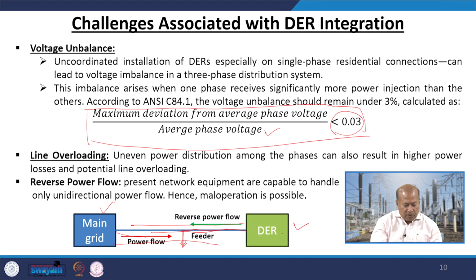Previously it was coming through this way, and now it can also go in the reverse direction. Reverse power flow: present network equipment is capable of handling only unidirectional power flow. Currently, all the devices are capable of carrying unidirectional power flows. Hence, mal-operation may be possible due to reverse power flow. Instead of going from the main grid to the load, it is now carrying power from the DR to the main grid. So the main grid is now receiving power from the DRs instead of providing it to the load customers.